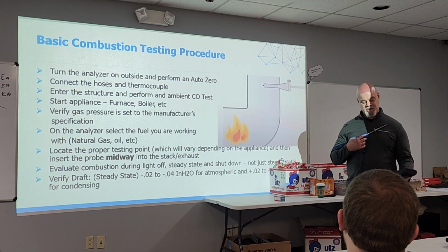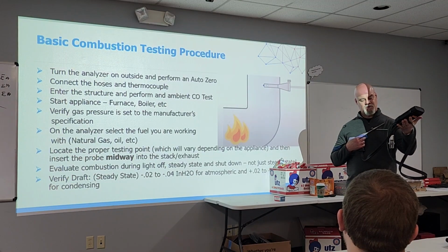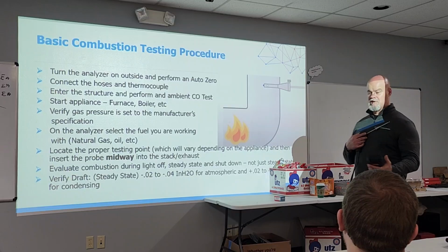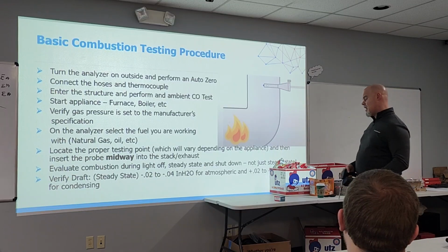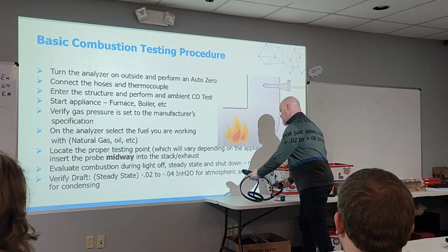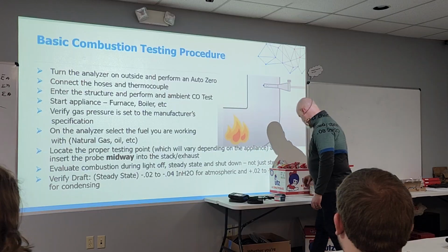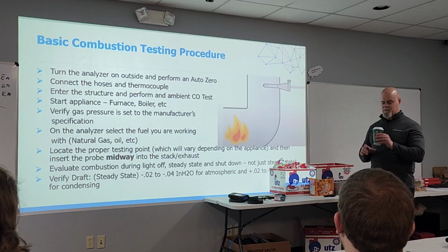Probe goes here across your chest, pick up the hose slack so you don't trip over it. You're going to go through and make sure you have 0 ppm of CO. Now, the correct standard I'll give you is 0 to 9 ppm.